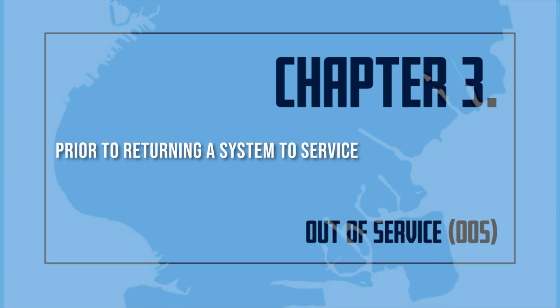Prior to returning a system to service, the impairment coordinator shall ensure that the necessary tests and inspections are conducted to verify that the system is operating normally, notify the fire department borough dispatcher, the building owner's tenants in the affected area, the insurance carrier, and the central station operator if so equipped, and remove out-of-service tags and discs.